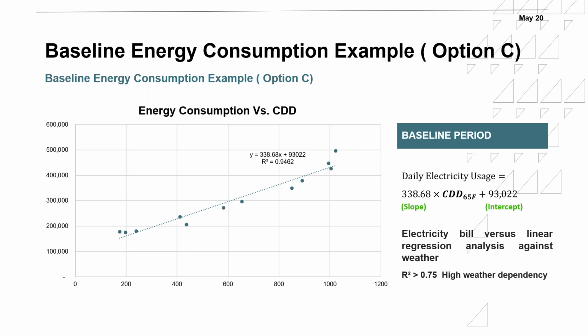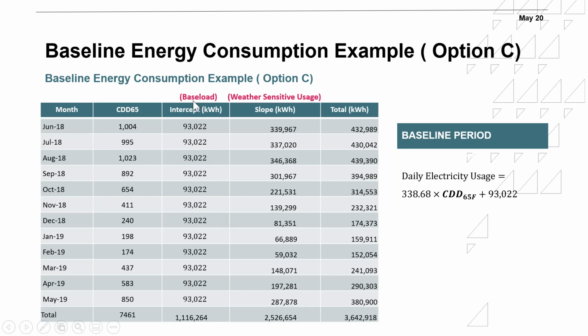Now, as we can see, the equation is equal to 338.68 times the cooling degree days plus the intercept, which is equal to 93,022. This is basically the base load. The base load is equal to 93,000, meaning that whatever I do, though it's not dependent on weather, I'm going to use that base load. And this slope part, which is the weather sensitive part, is driven by weather. As you can see here, this is the intercept. So 1.1 million is used during the year, which is not weather dependent. That is mainly being used by the lighting, by the fans. Whether it's cold or hot, they're going to be used. That energy is going to be used on the fans because the ventilation fans are not dependent on the weather. And let's say the parking fans, not depending on the weather. The lighting is not dependent on the weather. Anything else in that particular building is more or less depending on the weather.